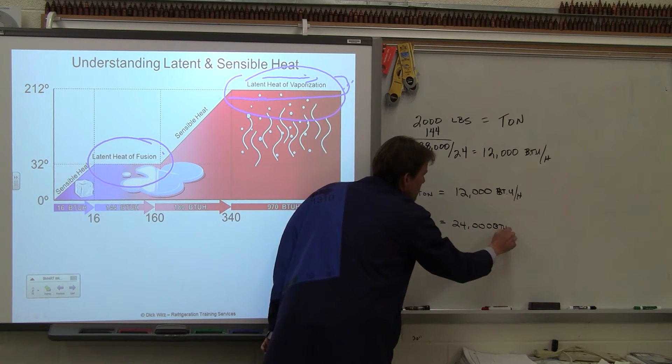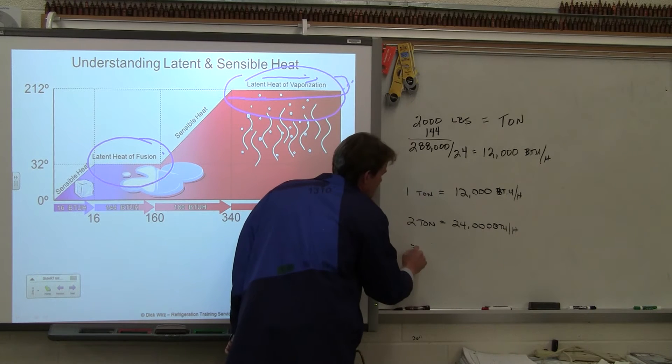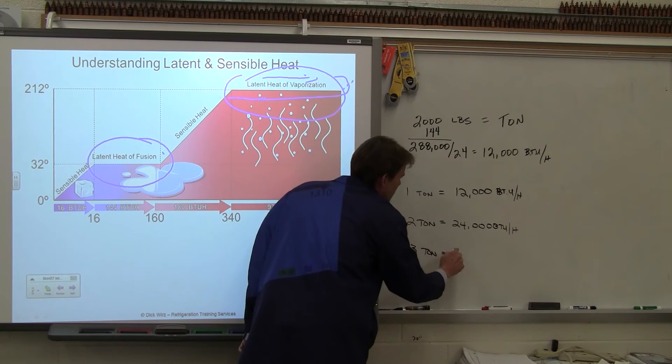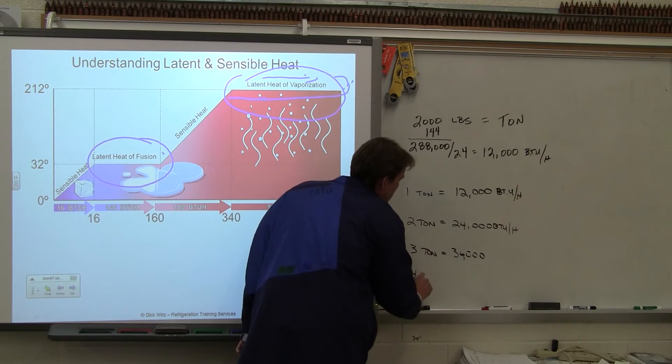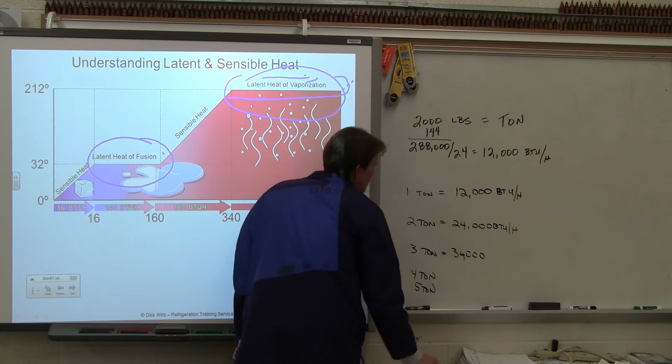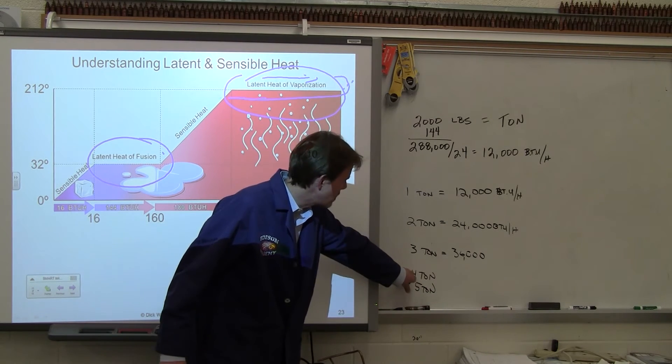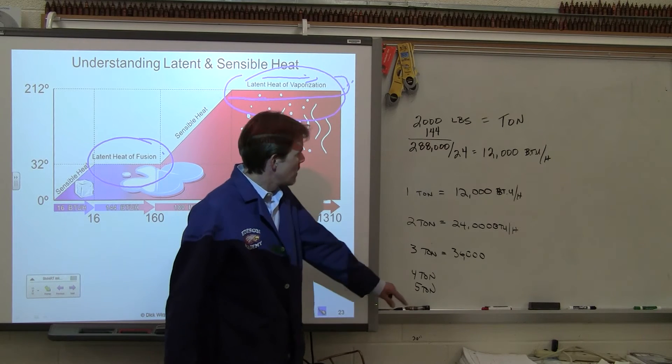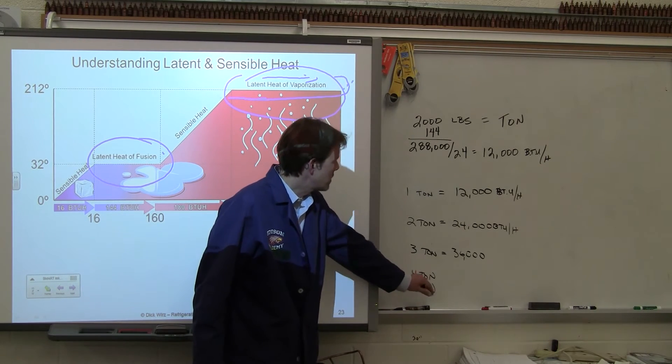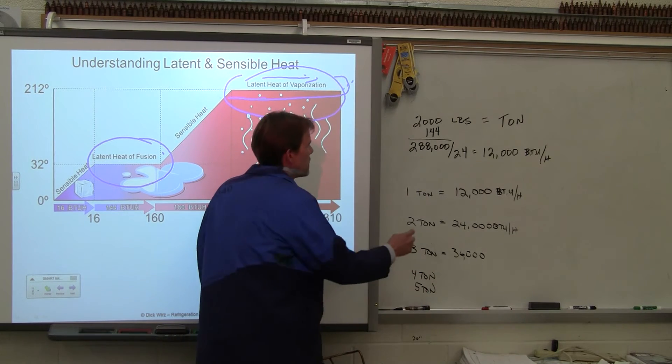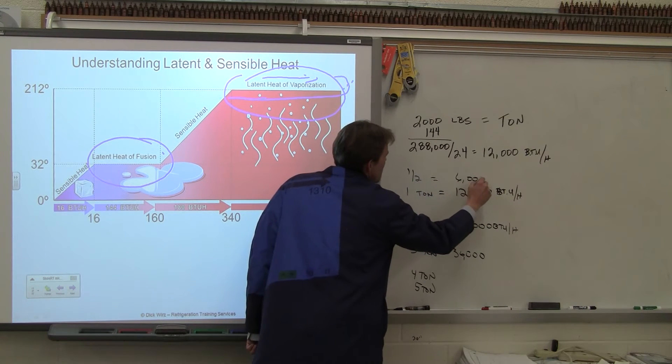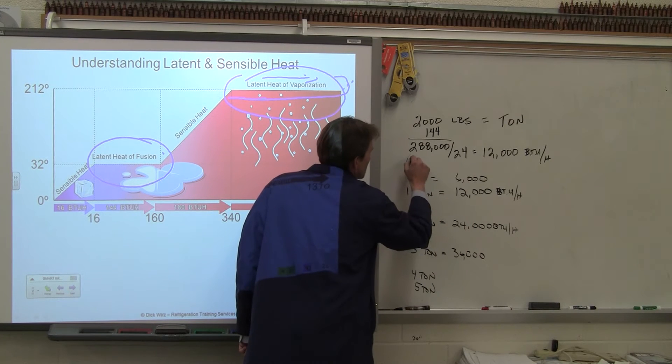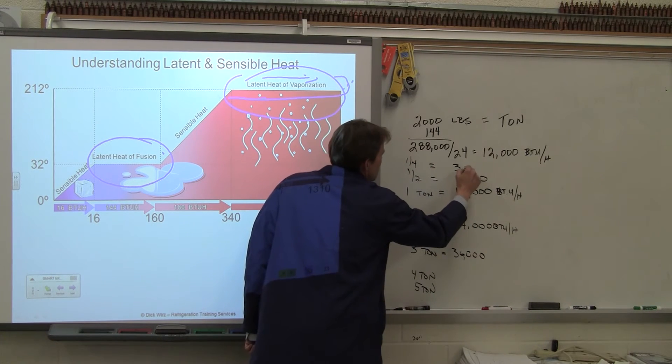Then 3 times is 36,000 BTUs. And then they can also go down the other way. Really, we don't have a 4 and a half, but you can kind of make one by combining a 5 ton indoor and a 4 ton outdoor, though you really want to match them, indoor and outdoor. We can also go the other way. We can go to a half a ton, how many BTUs would that be? 6,000 BTUs.